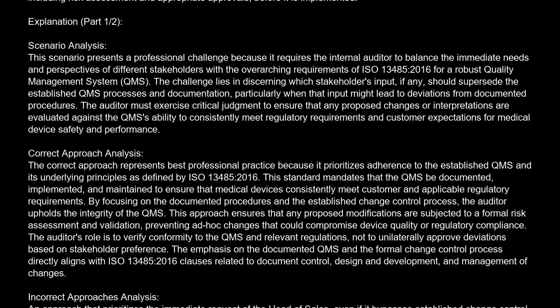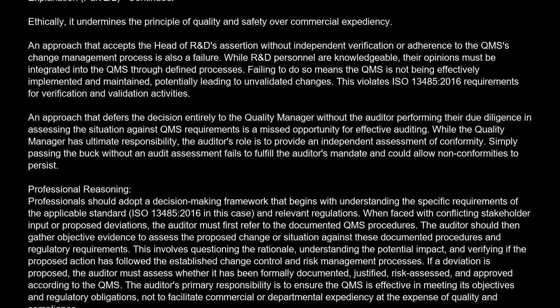Incorrect approaches analysis. An approach that prioritizes the immediate request of the head of sales, even if it bypasses established change control, represents a significant regulatory and ethical failure. This bypasses the fundamental requirement of ISO 13485, 2016 for a controlled and documented QMS. It introduces an unacceptable level of risk, as changes to device labeling or instructions for use can directly impact patient safety and regulatory compliance. Ethically, it undermines the principle of quality and safety over commercial expediency.